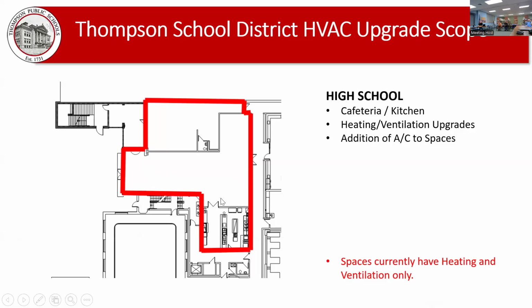The kitchen area and the home ec area - all that ductwork will be existing to remain with disconnect/reconnect, but the cafeteria itself will have a complete new layout with supply diffusers. There is a makeup air unit that goes across this corridor and the classrooms, with a stainless steel shroud outside where we currently get outside air to the unit above the ceiling. That will no longer be needed because outside air will be taken directly from above the vestibule, so we won't be utilizing that - it'll be abandoned in place, meaning we don't have to do anything with ceilings down here, saving cost.